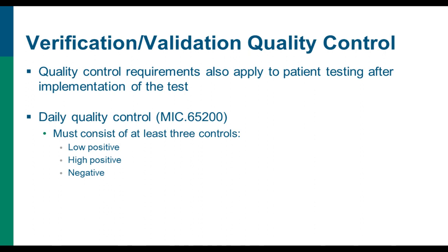Once you have your curve figured out, you'll want to start running patient specimens. With patient specimens, you'll want to run quality control. The quality control requirements also apply to patient testing after you implement it. As far as what's required for daily quality control for quantitative assays, it must consist of at least 3 controls: a low positive, a high positive, and a negative. Similar to a lot of these things, there's no definition of what constitutes a low or high positive.